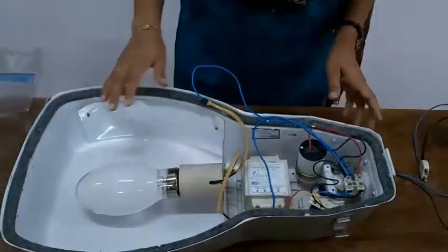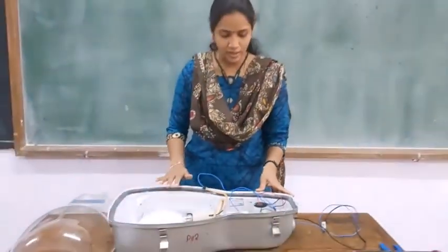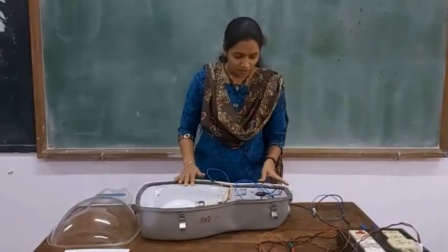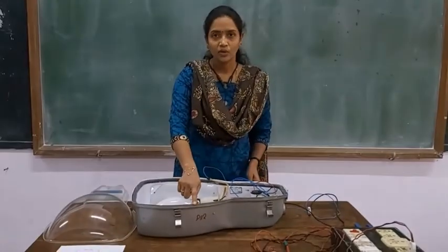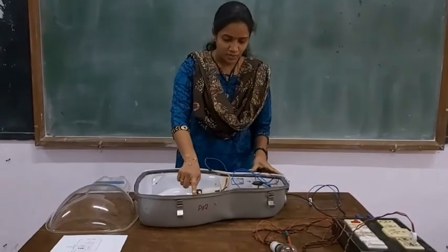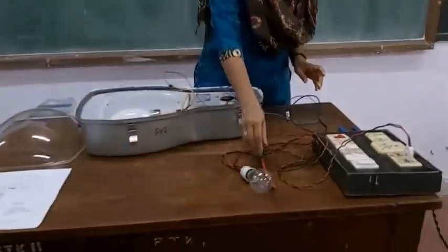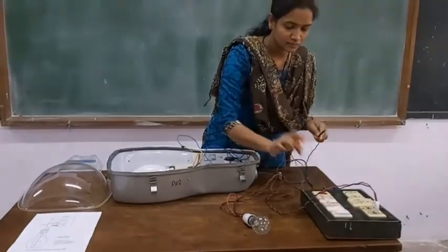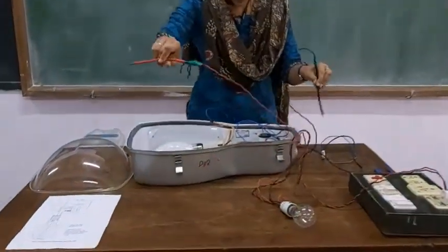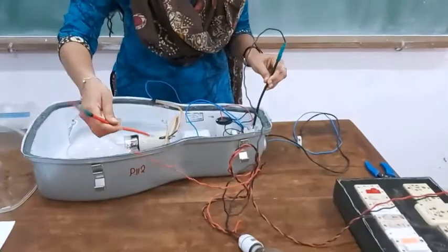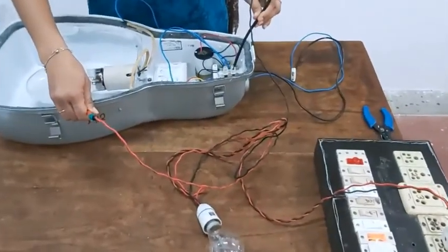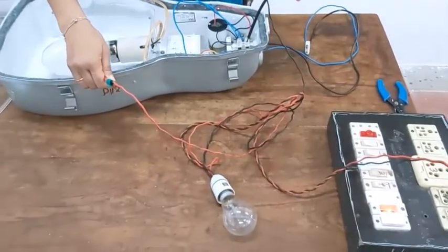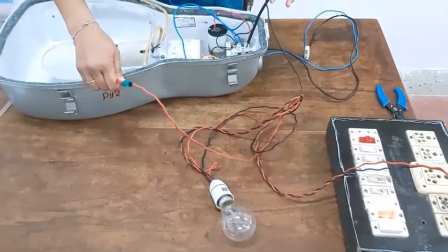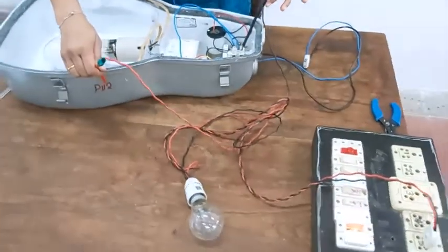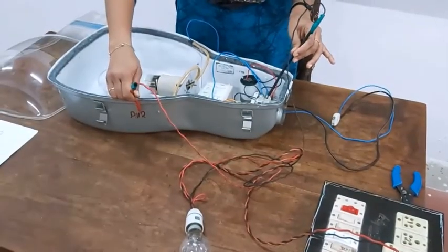Before switching on this high pressure sodium vapor lamp fixture, I am going to check for ground fault for the body of this lamp set. Here the series test lamp is in off condition. This shows that there is no ground fault in the body of this high pressure sodium vapor lamp set.